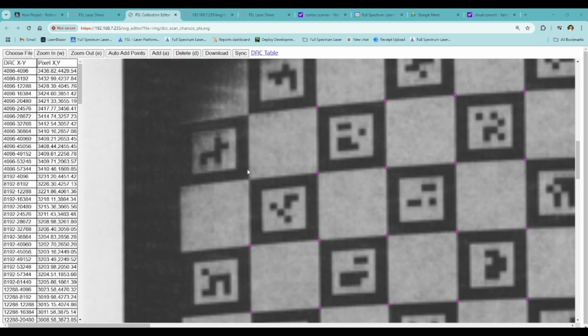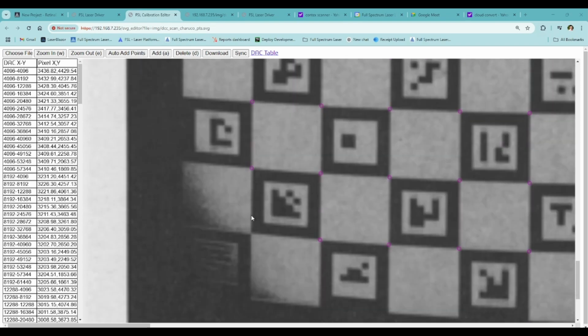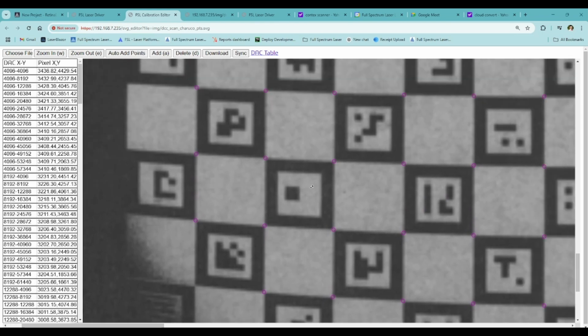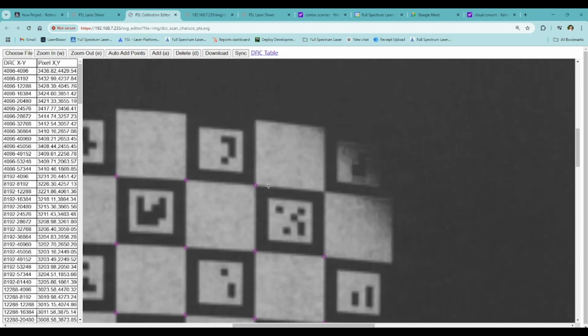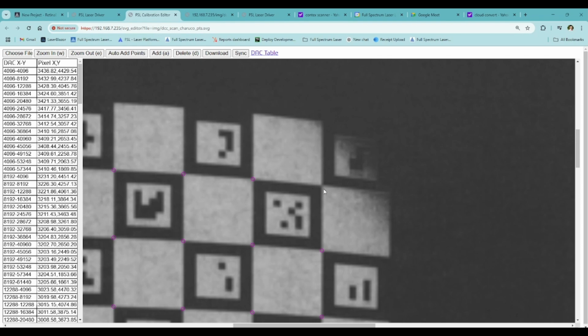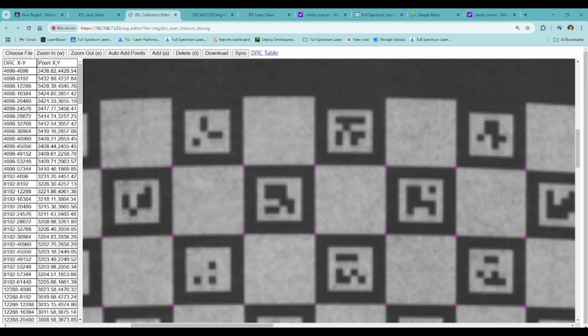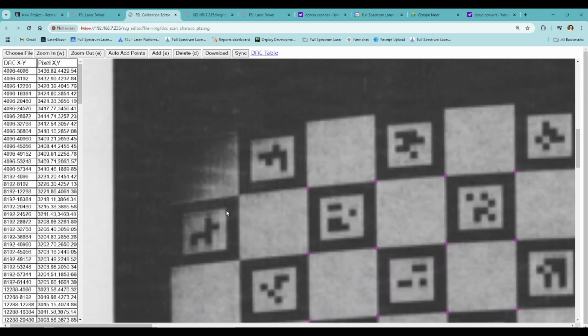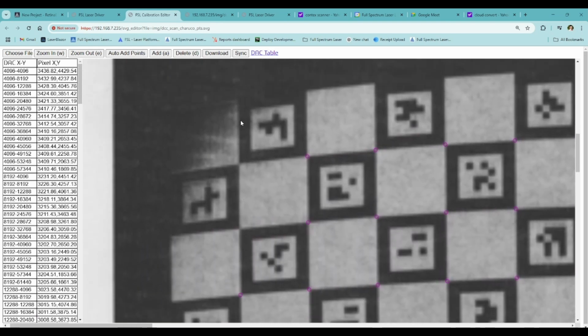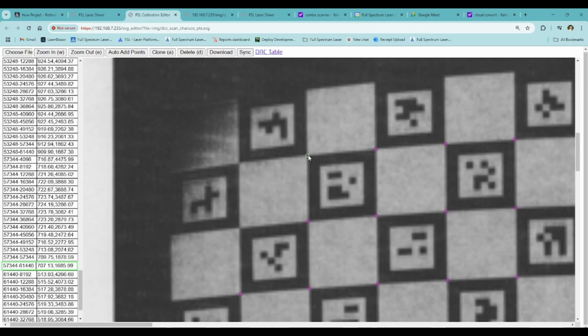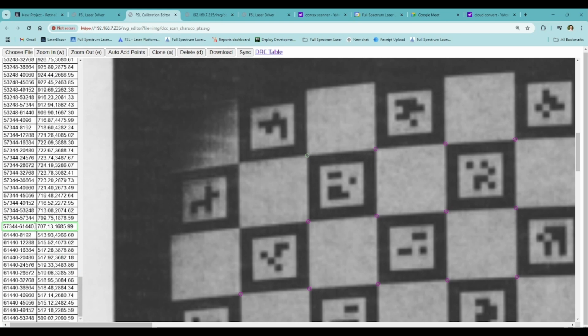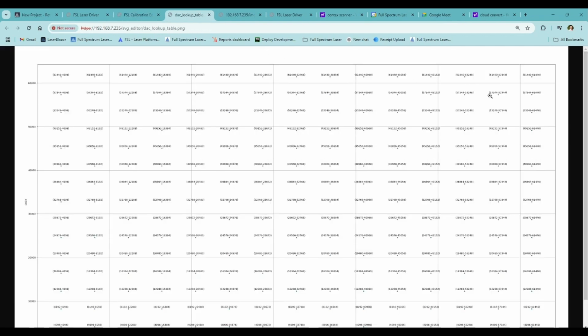We can identify the missing points using both the scan and the DAC table to determine exactly which points are missing. Keep in mind that I uploaded my scan into the system sideways, so we need to account for that when searching for the missing points. Essentially, the top left corner of my scan corresponds to the top right corner in the DAC table. This may not be the same for you, so be sure to keep in mind the orientation in which you uploaded the scan. For example, if I click on a known point, it will display which point it actually is. Then, we can use this information to locate the corresponding point in the DAC table.